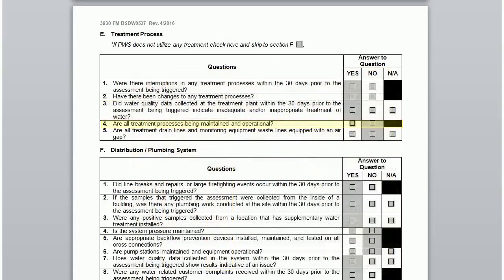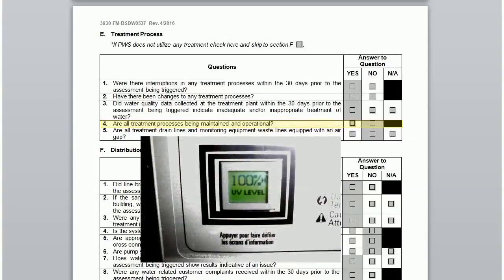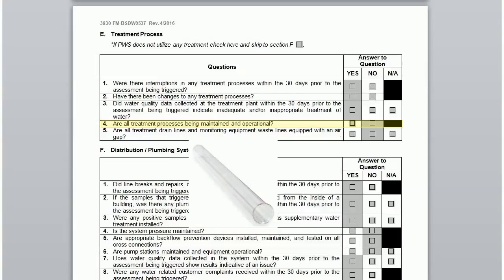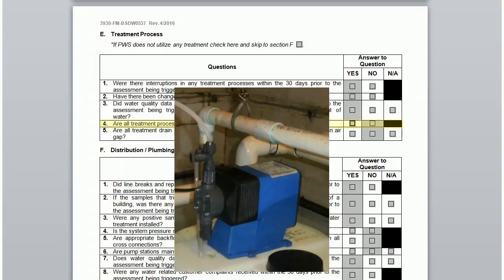The fourth question asks: are all treatment processes being maintained and operational? A UV light gradually loses its intensity over time and must be replaced when it falls below a certain intensity level. Follow the manufacturer's requirements. The quartz sleeve in the UV system must also be cleaned according to the manufacturer's requirements. Chlorinators need to be maintained; there can be problems with the motor or valves and O-rings getting dirty and worn.